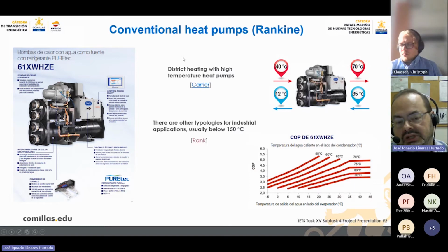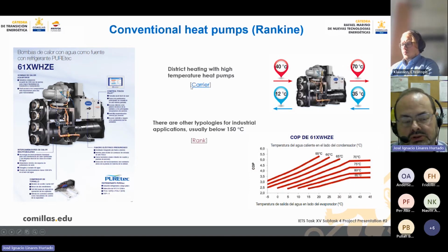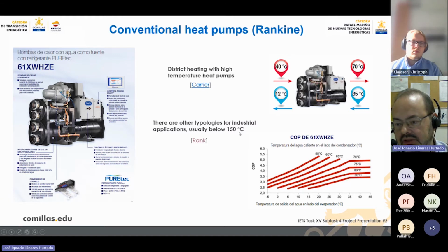As this is a more or less conventional heat pump, we have commercial equipment from Carrier, Rank, or other manufacturers, which achieve a maximum temperature of more or less 150 Celsius degrees. This is the top for conventional heat pumps. It's a good value, but perhaps in an industrial application, we want to reach larger temperatures in order to take advantage of this technology. That is, we can talk about electrification of heat.